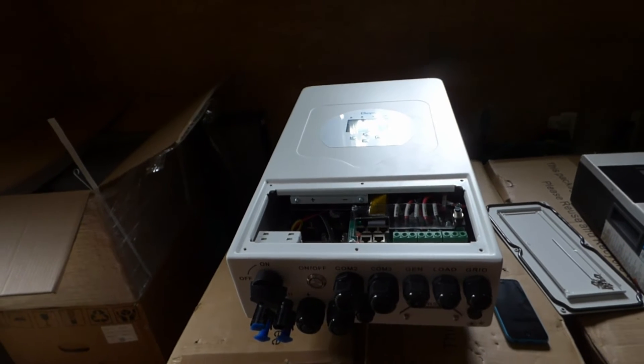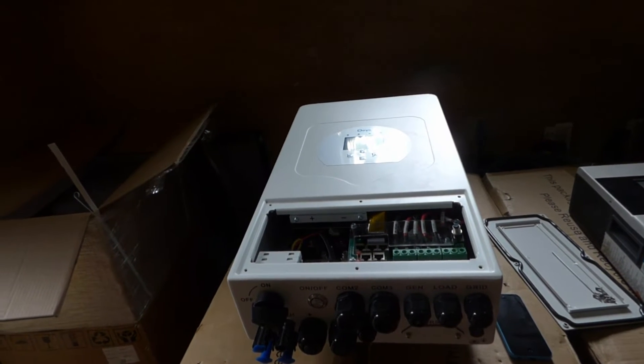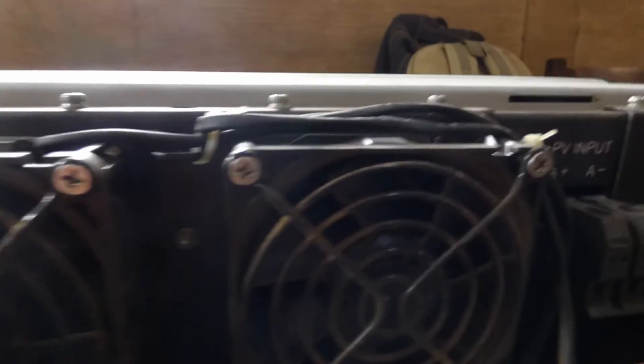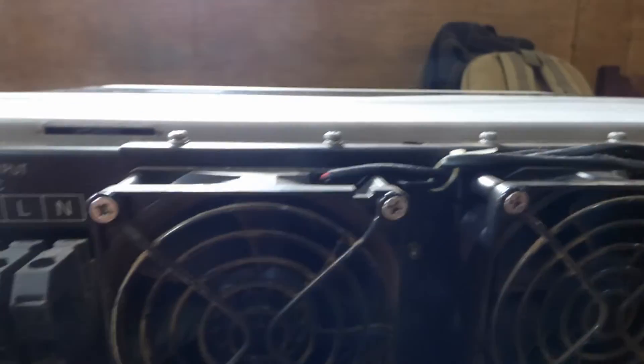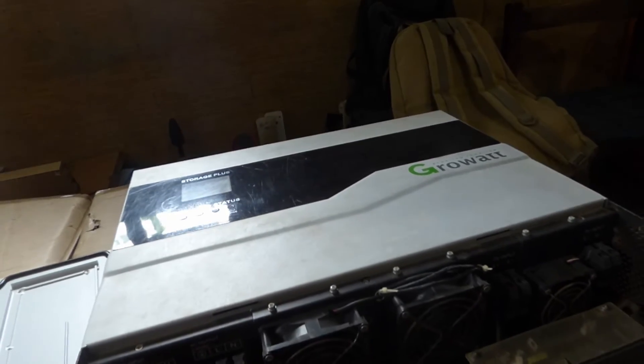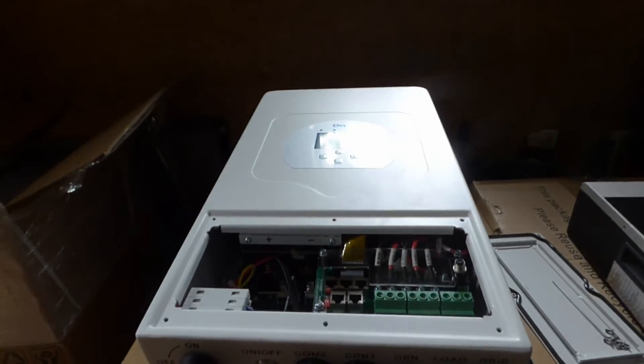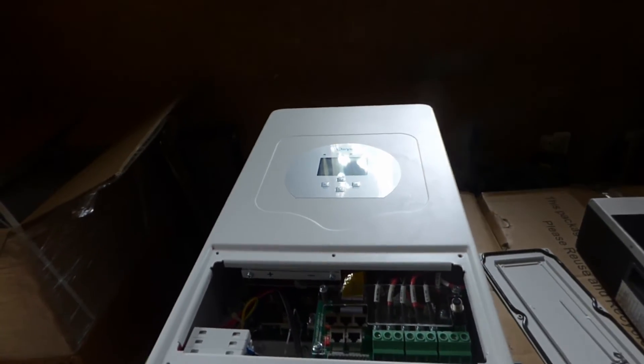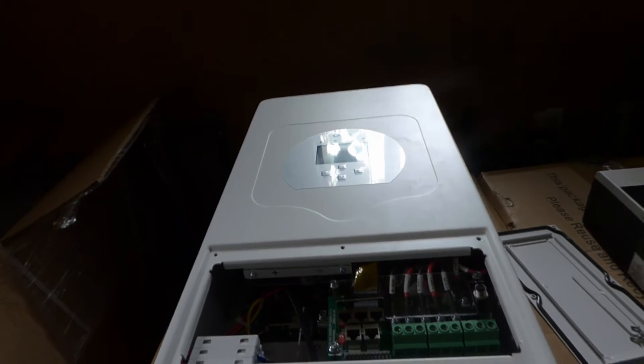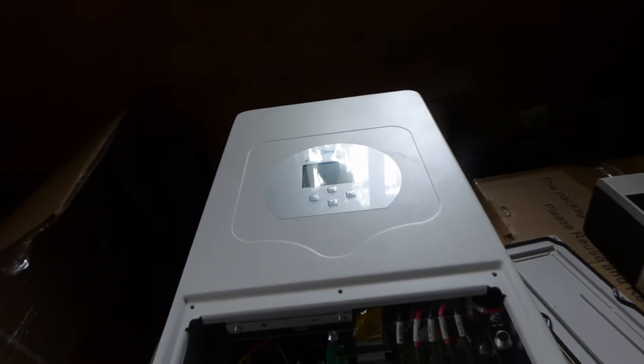It's IP65, so we can install it inside or outside. Let me tell you why IP65 is critical: look at the fans on the Growatt — you can see the dirt on them. These fans fail because of dirt, and part of our maintenance is constantly cleaning this up. There's also dust on the components. That is not an issue with the DEI because it's sealed. Nigeria dust is a big one.